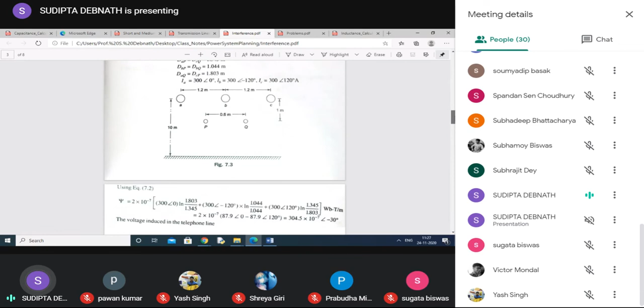Because you know, for single line to ground fault, say the single line to ground fault has occurred in phase A, then it never happens that B and C phases remain the same. The current also actually changes. But here they have asked to find the electromagnetic induction due to the fault current 2000 ampere in phase A. So only phase A you have to consider. It will have angle 0 and you find out epsilon from the same equation, but you have to consider only one phase because you don't know the currents in the other phases. Okay. And so these two are examples of electromagnetic induction.